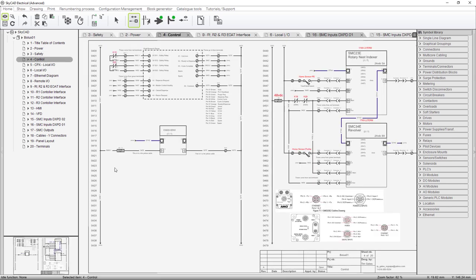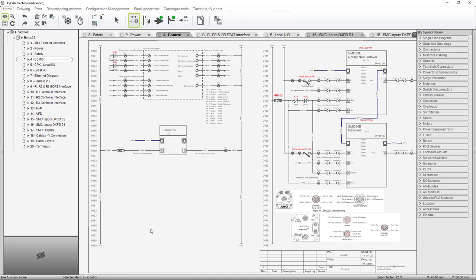Go to control. The main change here is that we now, this conductor right here goes to a different reference now because it's 48 volts DC. So we're supplying 48 volts to the aux connections and to the main connections. Other than changing the 24 volts to 48 volts, the other thing that we did was we removed the home sensors from the PLC, from the controller, the PAC, the CompactLogix. And then we wired them directly into the units.